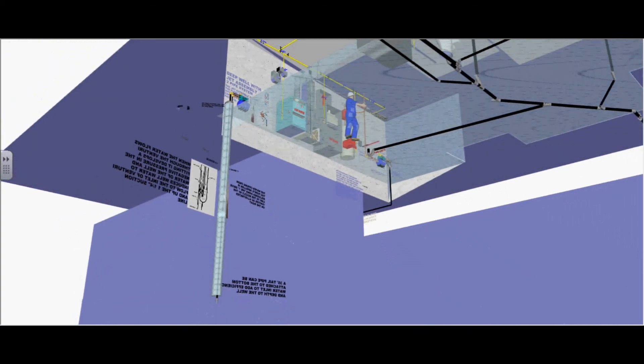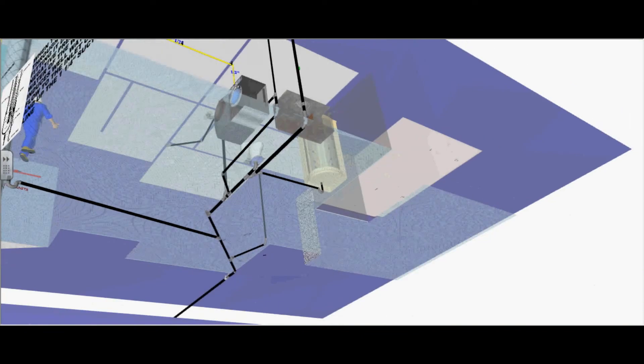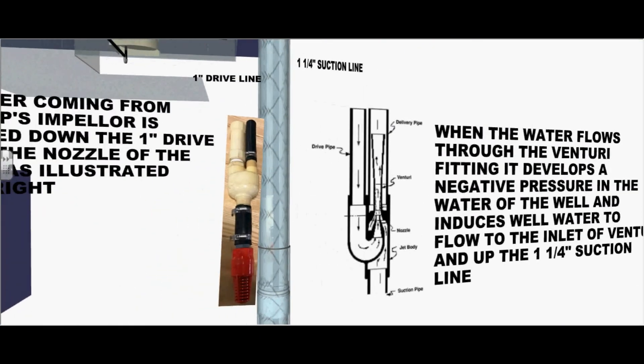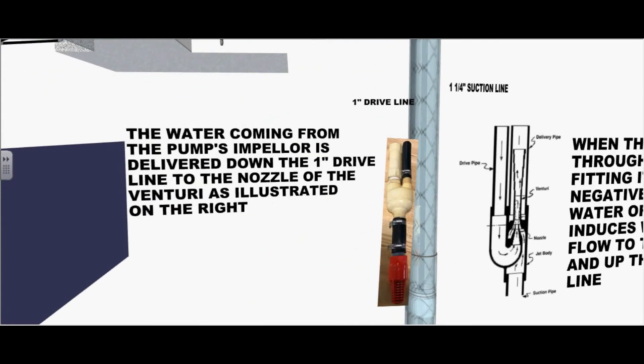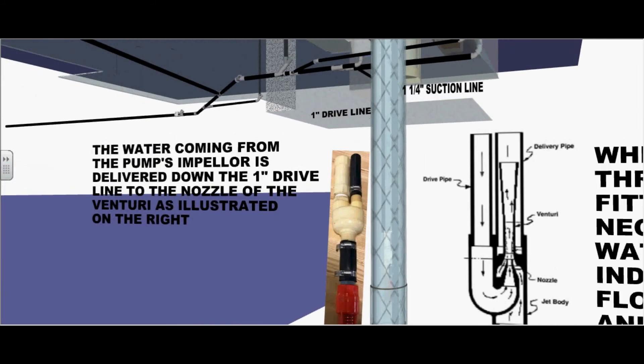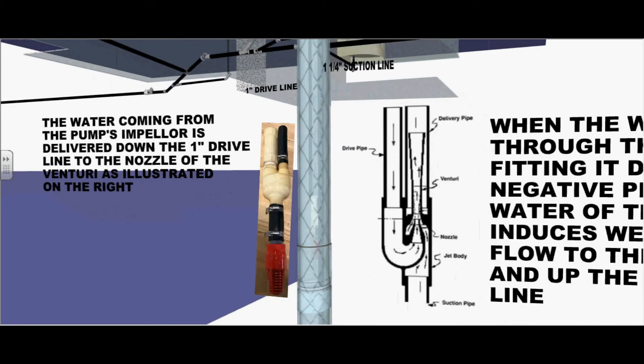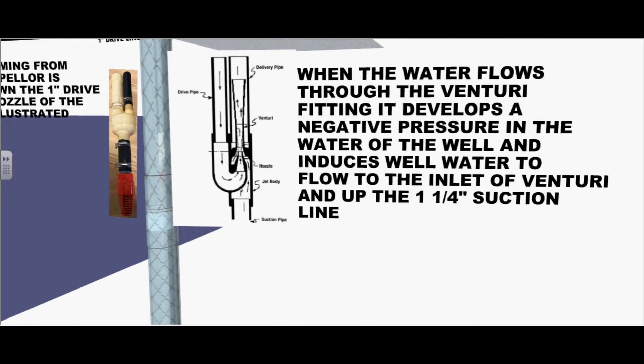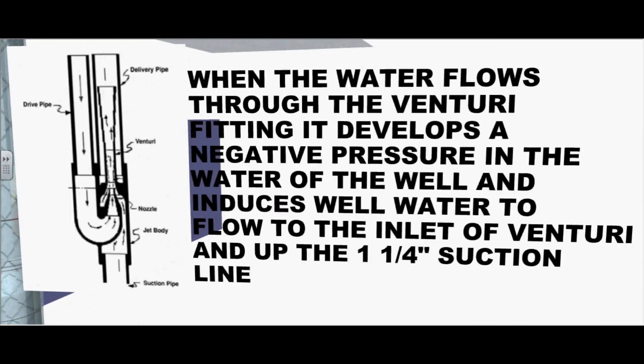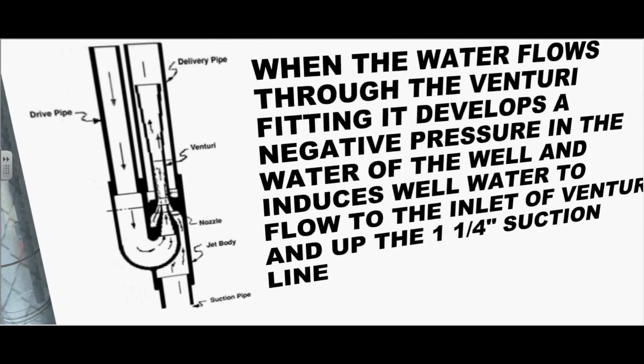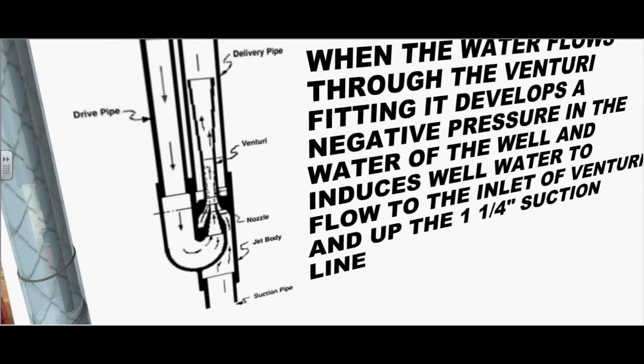Let's go further down the well and rotate around and we will take a look at the jet assembly. The water coming from the pump's impellers is delivered down the one inch drive line to the nozzle of the venturi as illustrated on the right. When the water flows through the venturi fitting, it develops a negative pressure in the water of the well and induces well water to flow to the inlet of the venturi and up the inch and quarter suction pipe.